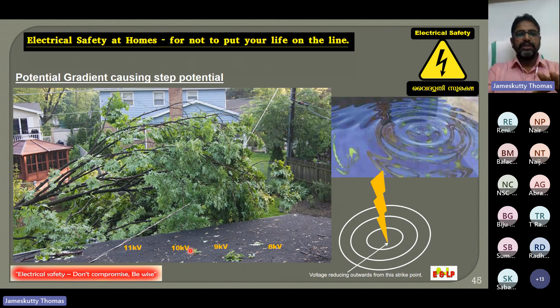Now, how to prevent electrical accidents in domestic premises? Effective earthing as per IS 3043 is a must. Earthing should be done in the proper way, and it should not be a namesake one. Then each of the circuits should be provided with overload protection such as a fuse or MCB of adequate rating. Then an RCCB or ELCB of high sensitivity, for example 30 mA, should be incorporated. Then the plug should be a 3-pin plug with finger grips.